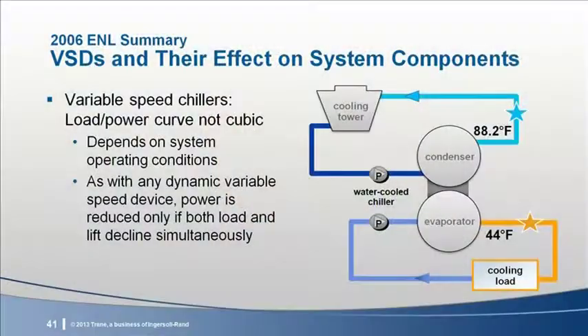The good news about chillers is that a chiller compressor's load does follow the system load down to a very low value. The bad news is that the lift the system imposes on the compressor seldom decreases anywhere near to the square of the flow as would be required to achieve the ideal speed and power reduction.